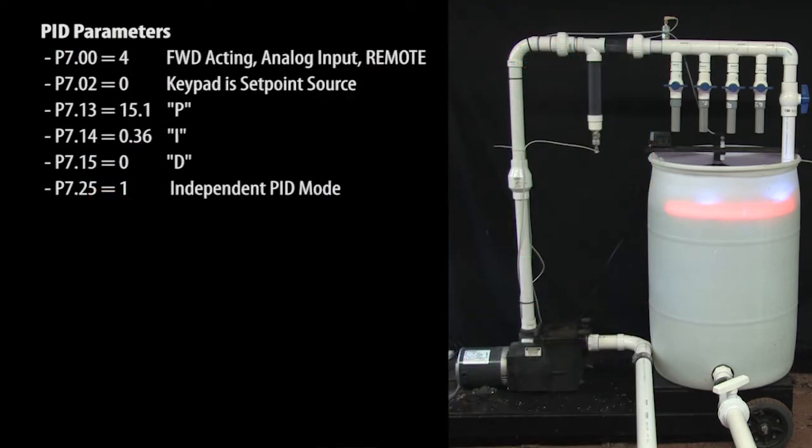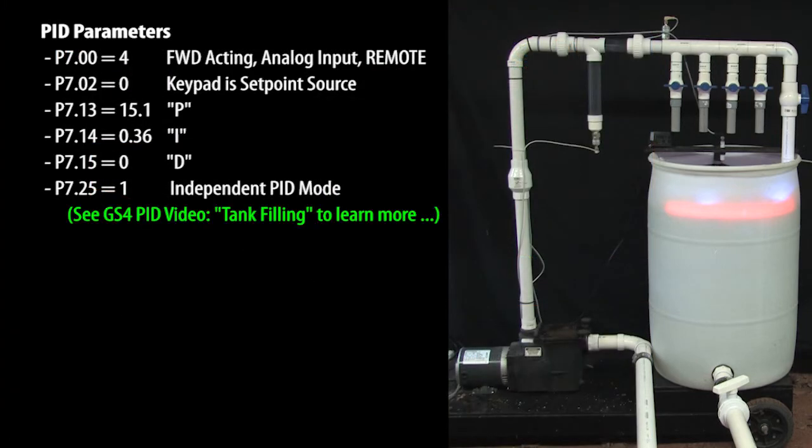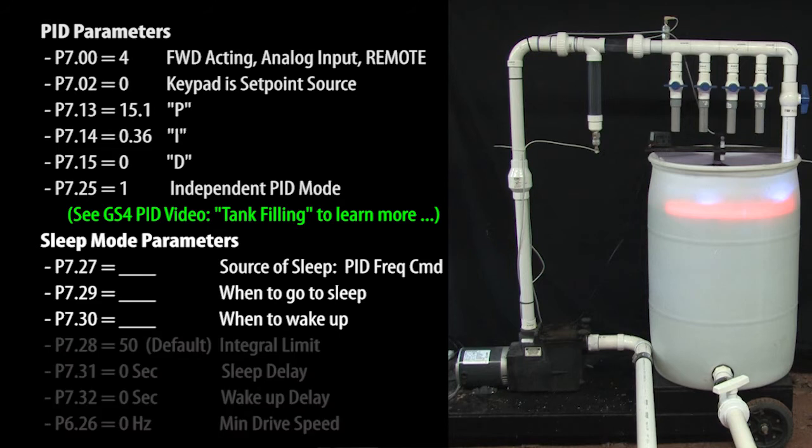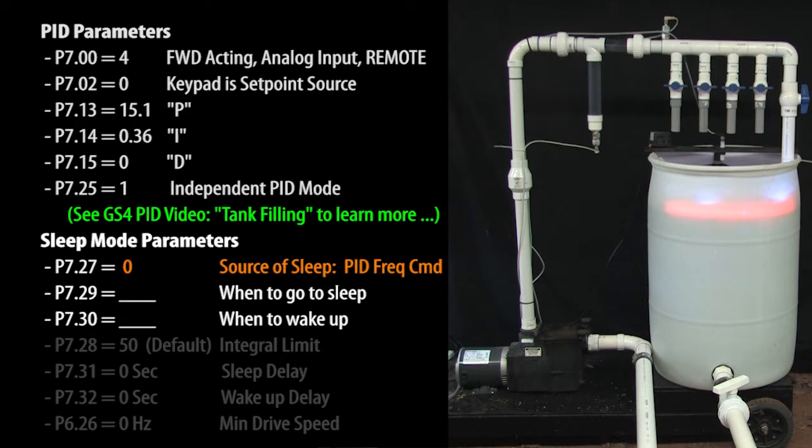These are the PID parameters I'm using. There's a separate video showing you how this was done so we won't do that again here. And these are the sleep mode parameters and we only need a couple of these to get started. First, we need to tell sleep mode to watch the PID frequency command to make its decisions. That puts us in sleep mode 0. Centrifugal pumps get pretty inefficient below 30 Hz, so let's have sleep mode turn the motor off at 30 Hz.